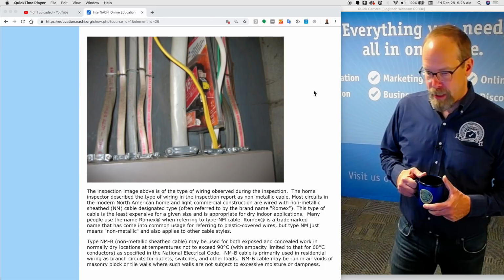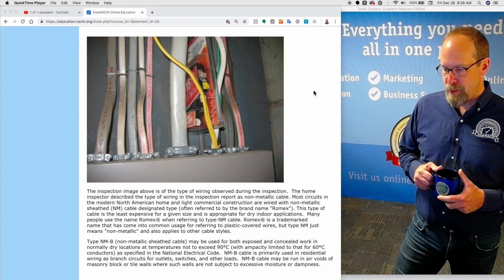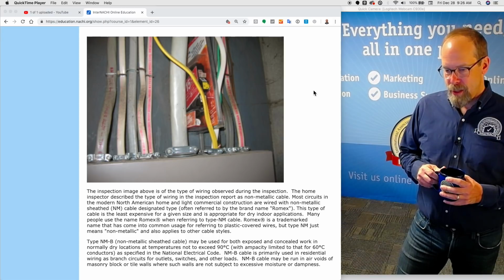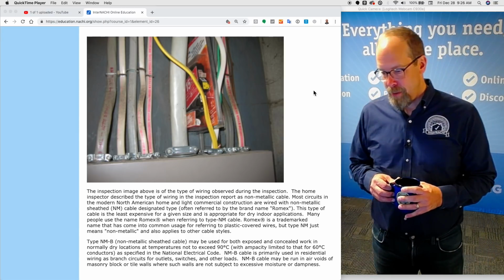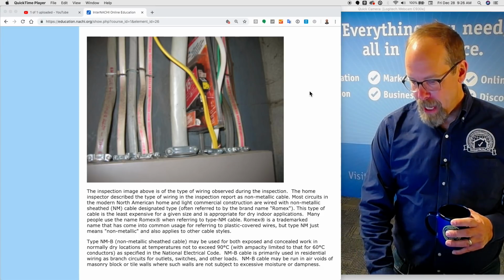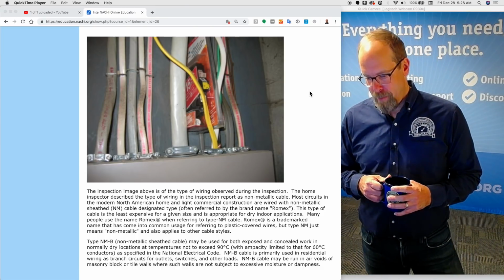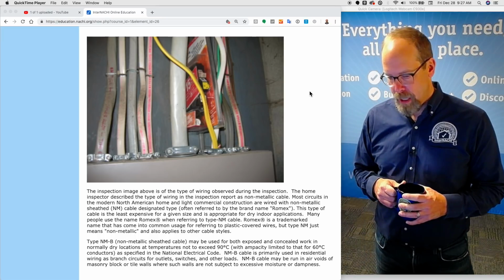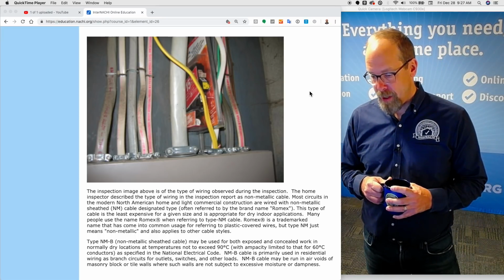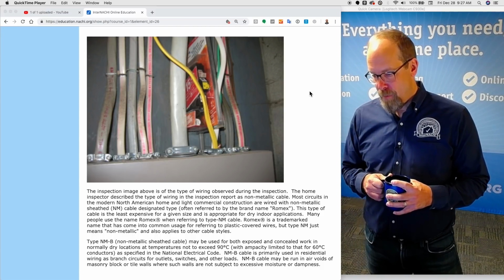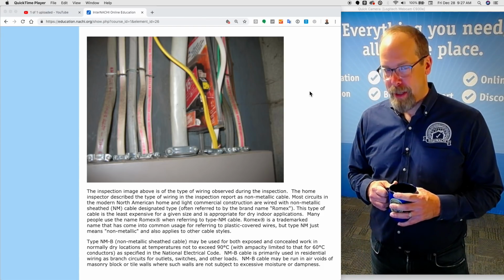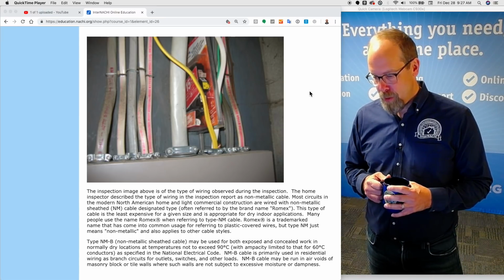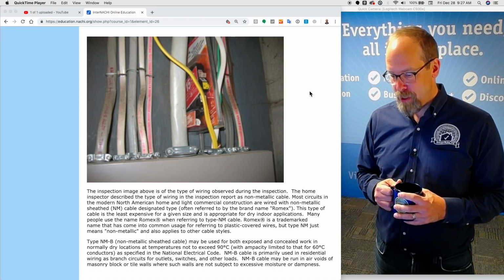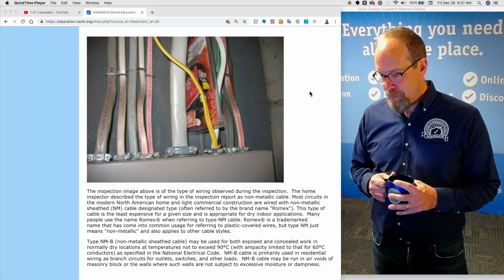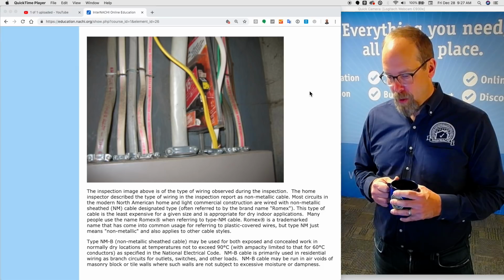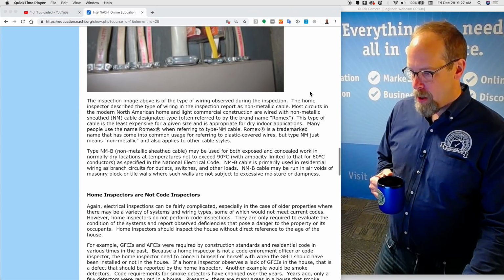Many people use the name Romex when referring to type NM cable. But Romex is a trademark name that has come into common usage for referring to plastic-covered wires, but type NM just means non-metallic and also applies to other cable styles. Type NMB, non-metallic sheathed cable, may be used for both exposed and concealed work in normally dry locations at temperatures not exceeding 90 degrees Celsius, with ampacity limited to that for 60 degrees Celsius conductors, as specified in the National Electrical Code. NMB cable is primarily used in residential wiring as branch circuits for outlets, switches, and other loads. NMB cable may run in air voids of masonry block walls or tile walls where such walls are not subject to water, dampness, or moisture.